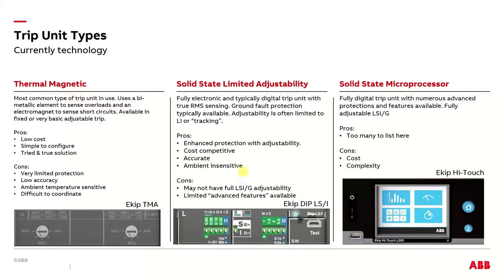One of the pros, it's ambient insensitive. Because it's electronic, I think all of them today are relatively insensitive to the ambient temperature for the tripping. Now, the breaker mechanics themselves, the breaker itself has a maximum temperature range and a derating based on current, but the trip unit isn't sensitive to the ambient temperature. Cons, it may not have full adjustability, and usually they're limited in how many advanced features you can put on the breaker. But they're a pretty good middle ground, and they're coming down in cost.